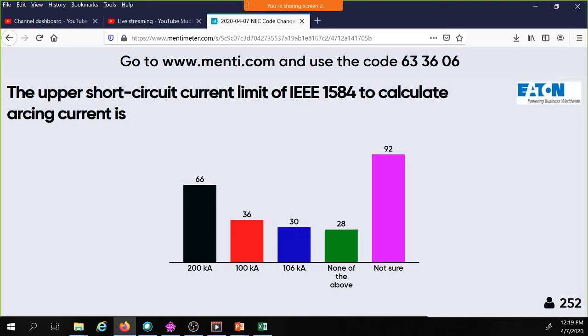So if I'm at a secondary network, downtown New York City, Abasi is sitting there in his science lab, approving drawings, working hard to make things safer, and he comes across a building with 180,000 amps available. The engineer gave him a set of drawings, and it says, I can't calculate arcing currents to meet the requirements of 240.67 to do a comparison of the arcing current with the clearing times, nor the technologies employed, because there is no mathematical equation for me to calculate arcing current when my fault current is greater than 106,000 amps. What do?